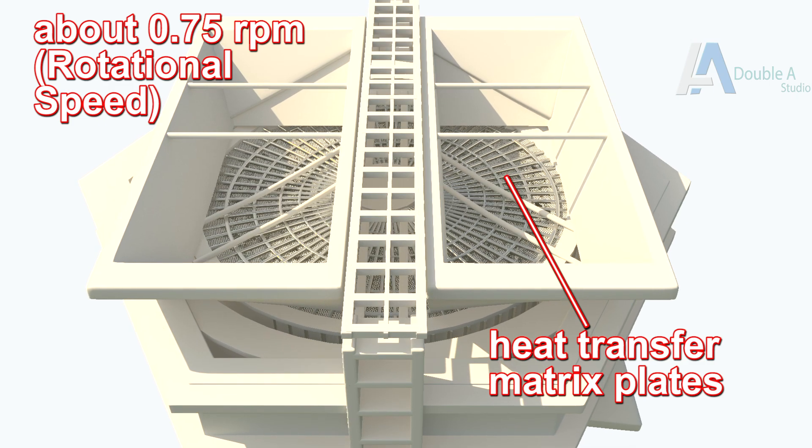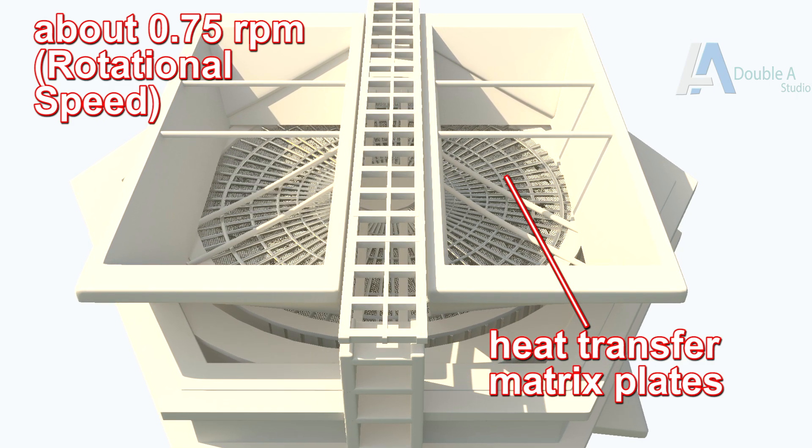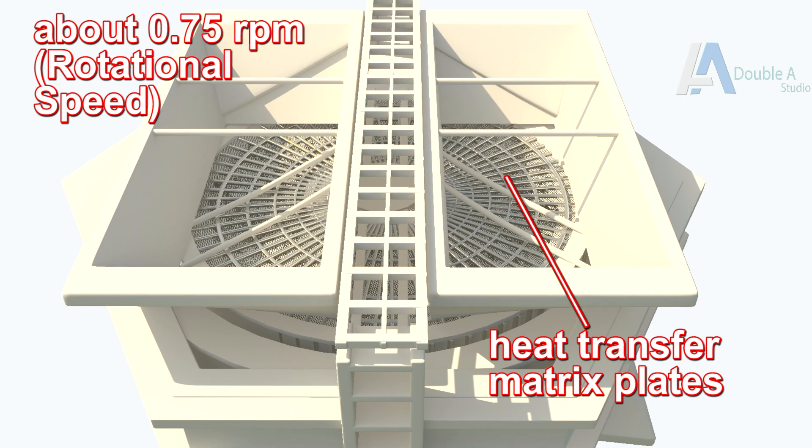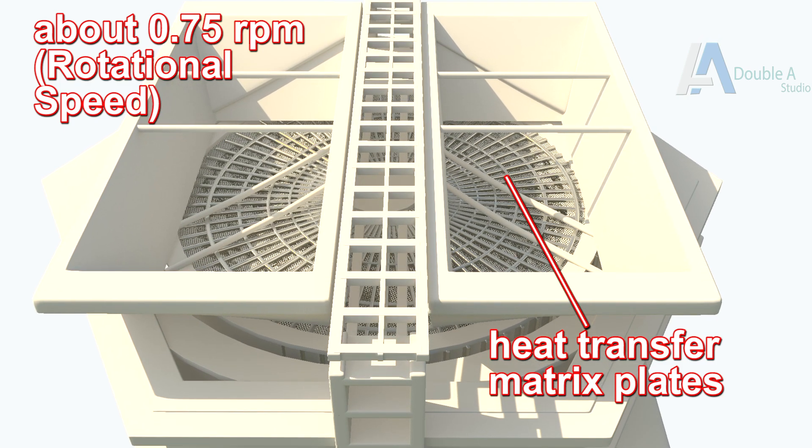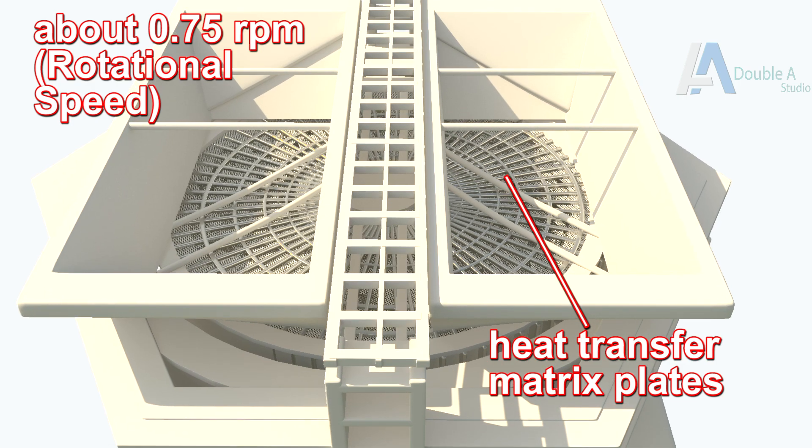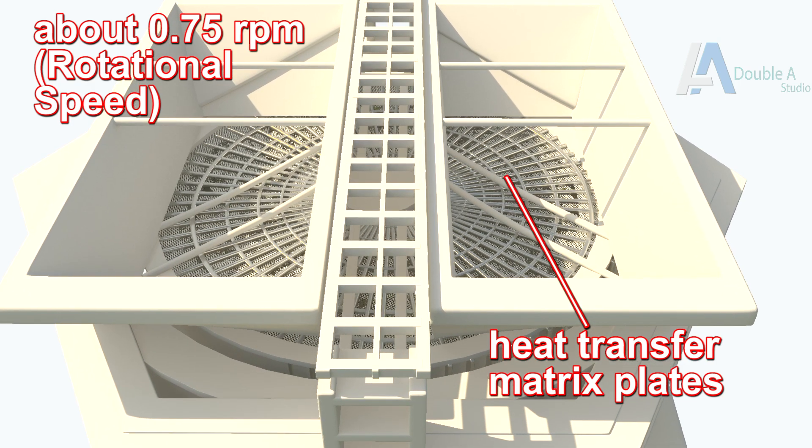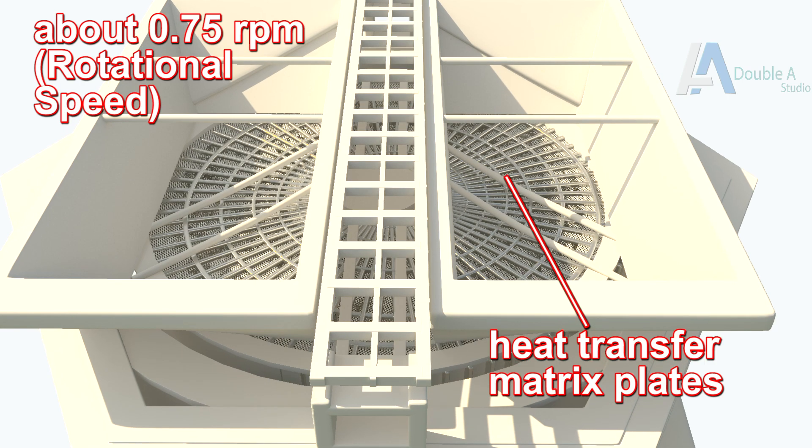Due to rotation, heat transfer plates are exposed to hot flue gas in half of the rotation and to ambient air during other half rotation. That's how heat from flue gas is absorbed by matrix plates in first half and is transferred to air in second half of rotation.